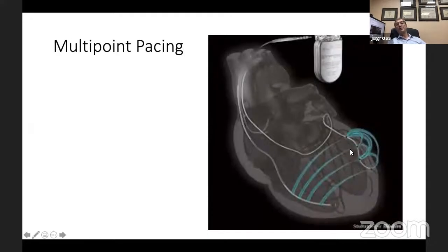Also, by having multiple electrodes, there is data now on patients with non-responders showing we can convert at least a percentage of those non-responders to responders by doing multi-point pacing. Often we don't really know the most desirable place, or there's enough scar that allows for a limited area of depolarization here, but not here. But if we could deliver energy to multiple spots, we might be able to convert a segment of the non-responder population into responders. And by having multiple electrodes, two and eventually all the companies will allow for multi-point pacing as well.